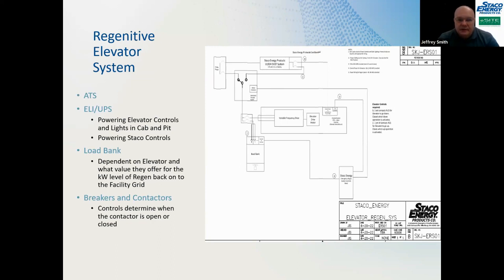UPS systems and emergency lighting systems have transistors. And what that does is, if you try to backfeed the inverter system, it raises the DC bus. And if you raise it too fast, that's when they say the smoke comes out of the transistors. We don't like that. So what we've done is we've added a load bank onto the system. And what that does is it allows the regenerative power to be fed back through the load bank and burn off instead of being fed back to the UPS.